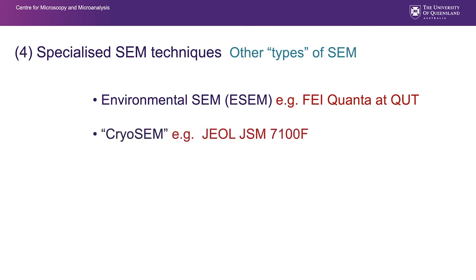A cryo-SEM allows you to look at frozen, cryogenically fixed samples. It is really a standard SEM that has a cryo-preparation unit and a cold stage cooled by liquid nitrogen inside the SEM. This allows us to look at wet and volatile samples that are difficult to image in an ordinary SEM where high vacuum is required. Keeping them frozen keeps them stable. We can coat them, fracture them, and image them, making it a unique instrument.